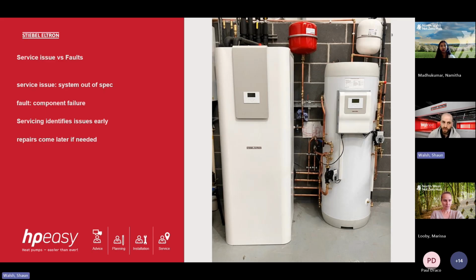Another point here, a service issue, so the system being out of spec. Again, that comes back to the control logic, or the heat pump is being used in a way that it's not been intended to. Some systems have gas boilers or secondary heat sources like immersion heaters. What can happen is if the system's not performing well, it can divert to these secondary heat sources for assistance. If these components are regularly coming on, then there could be an issue with the system side of the heat pump, which again leads to higher energy costs because you're using a secondary heat source. So it's always important that we check how the system is meant to run versus how it's actually running in reality.